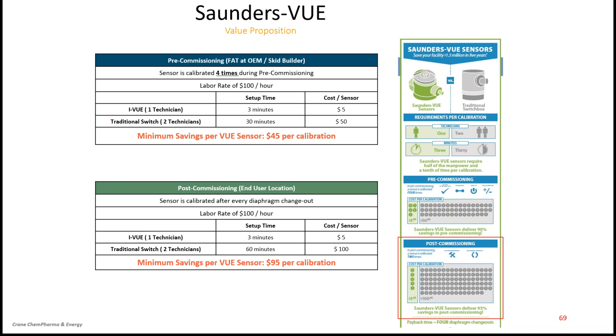If you look at post-commissioning, again, every time a diaphragm is replaced, the sensor has to be calibrated. Again, with a traditional switch, it will take up to 60 minutes, but with the VUE sensors, it just takes 3 minutes.